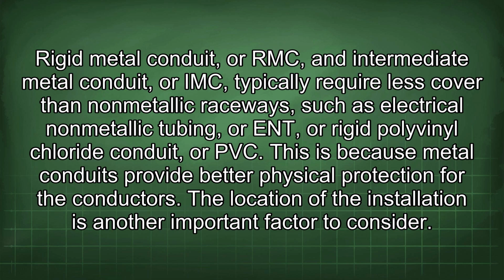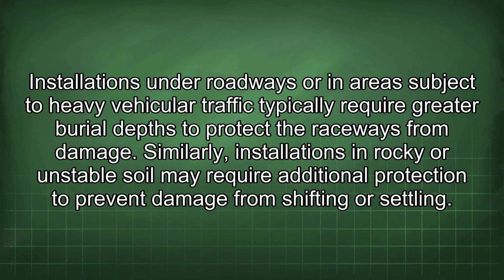The location of the installation is another important factor to consider. Installations under roadways or in areas subject to heavy vehicular traffic typically require greater burial depths to protect the raceways from damage. Similarly, installations in rocky or unstable soil may require additional protection to prevent damage from shifting or settling.